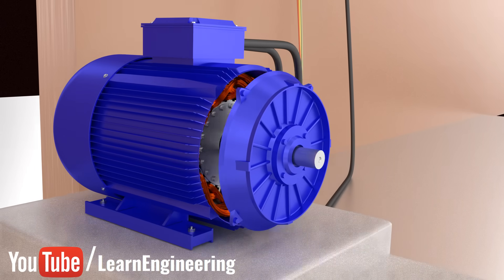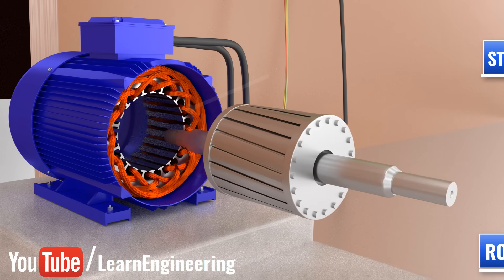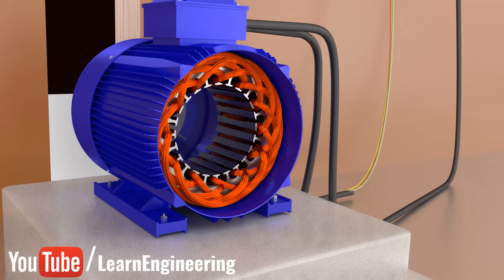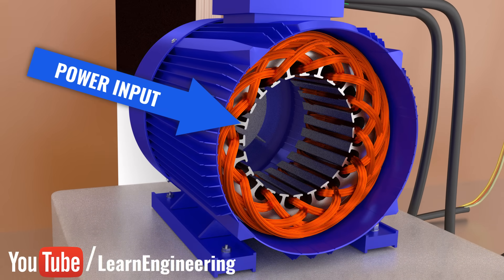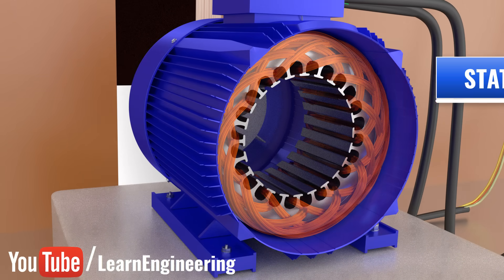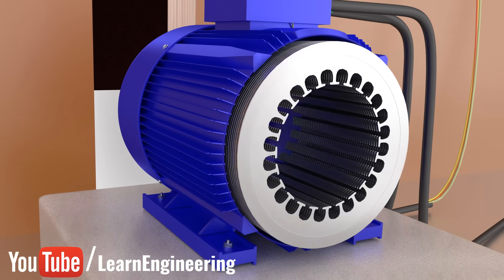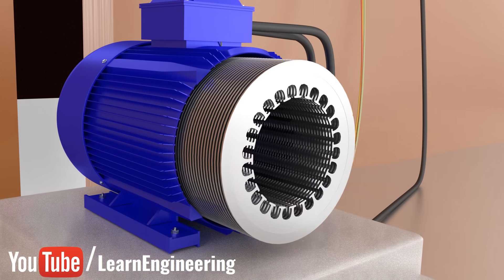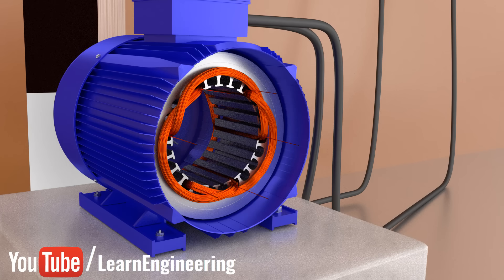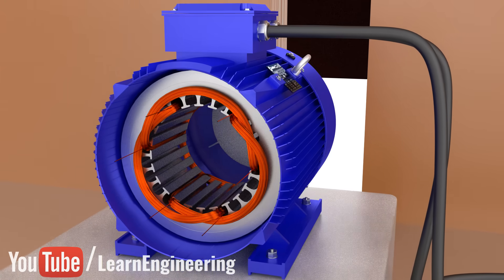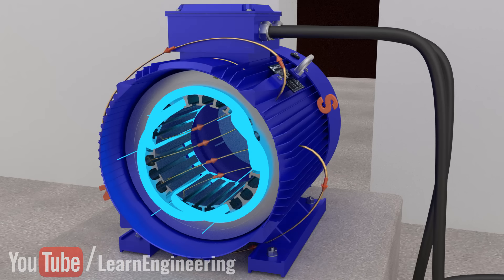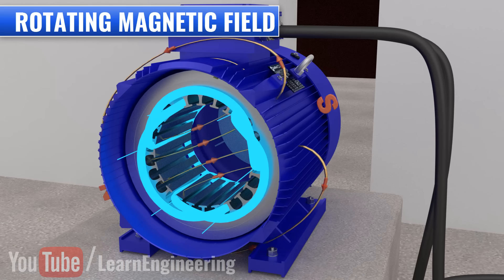The induction motor has two main parts: the stator and rotor. The stator is basically a three-coil winding and three-phase AC power input is given to it. The winding passes through the slots of the stator, which are made by stacking thin, highly permeable steel laminations inside a steel or cast-iron frame. When a three-phase current passes through this winding, something very interesting happens — it produces a rotating magnetic field.